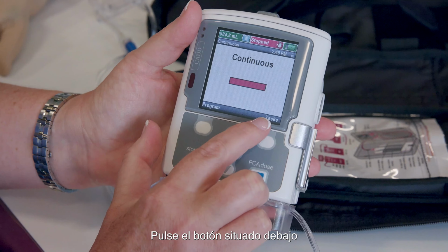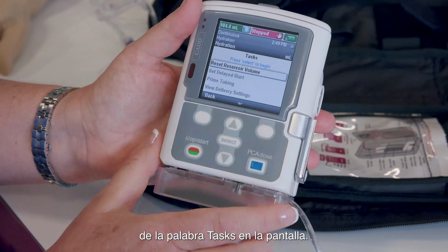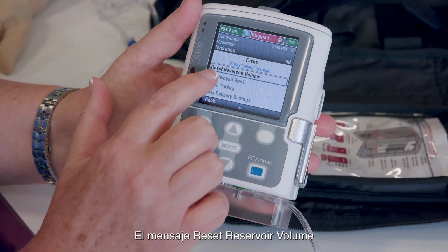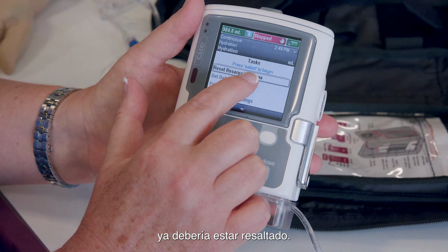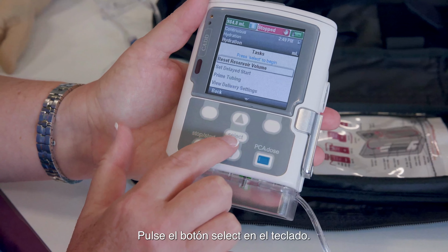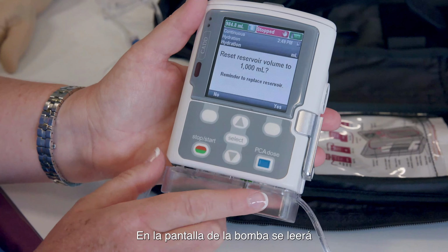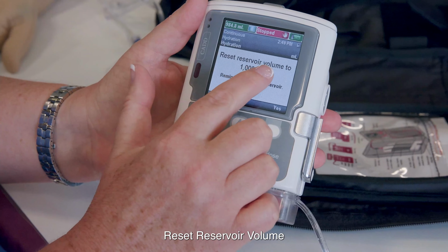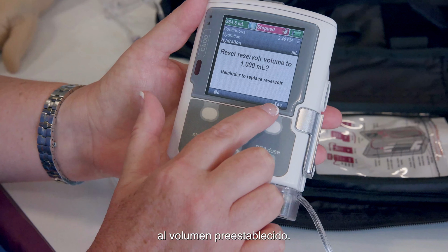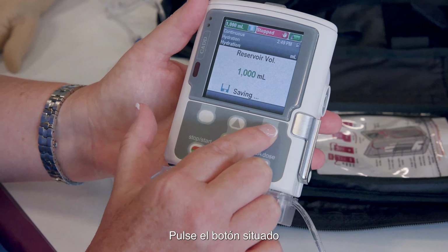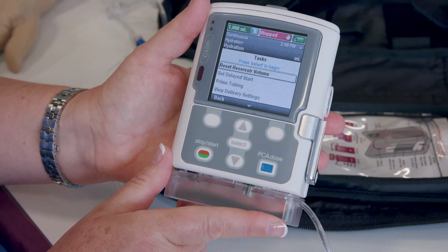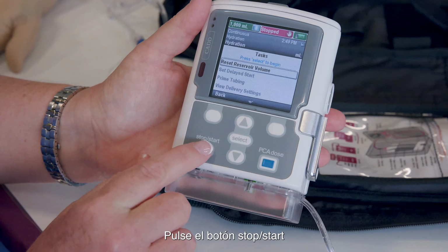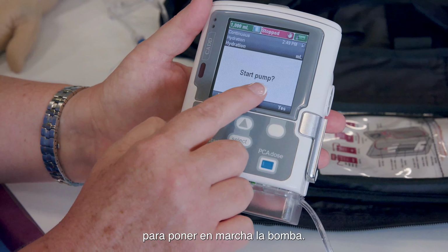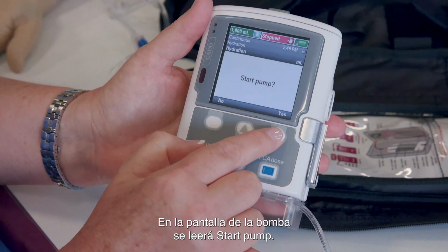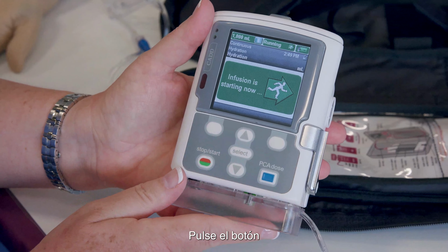Press the soft button under the word Tasks on the screen. Reset Reservoir Volume should already be highlighted. Press the Select button on the keypad. The pump will read, "Reset Reservoir Volume to the preset volume." Press the soft button under the word "Yes" on the screen. Press the Stop-Start button to start the pump. The pump will read, "Start Pump." Press the soft button under the word "Yes" on the screen.